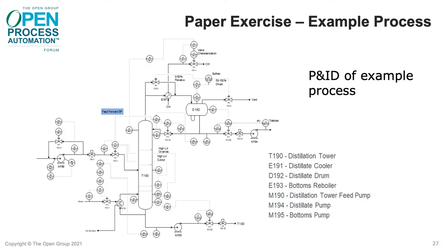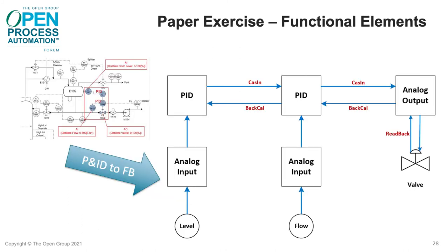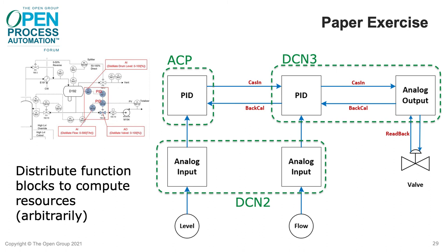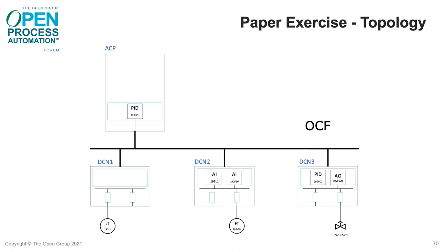To validate the OPAS specification and help clarify topics, we've spent a lot of time doing a manual walkthrough of building a system using the OPAS specification. We started with a piping and instrumentation drawing of a small example process, extracted the functional elements for the section we want to control, resulting in a simple function block diagram. We arbitrarily assigned the function blocks to different control nodes to make the example interesting, resulting in a topology of four control nodes connected to the OCF Ethernet network — some nodes have function blocks, some have I/O, some have both.